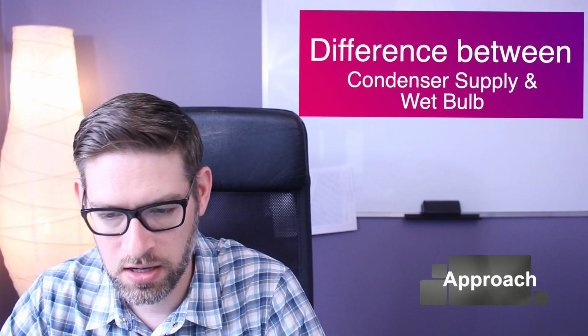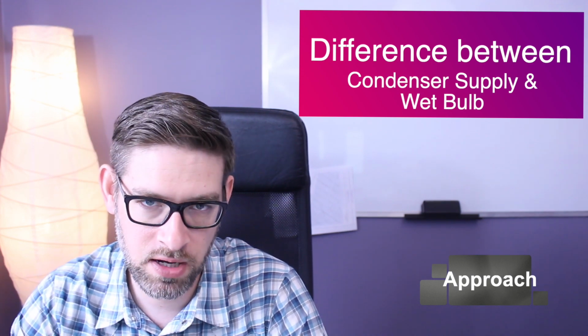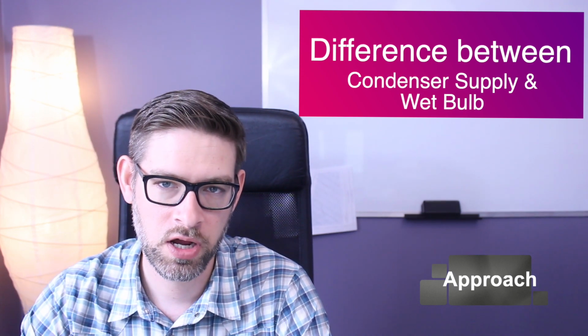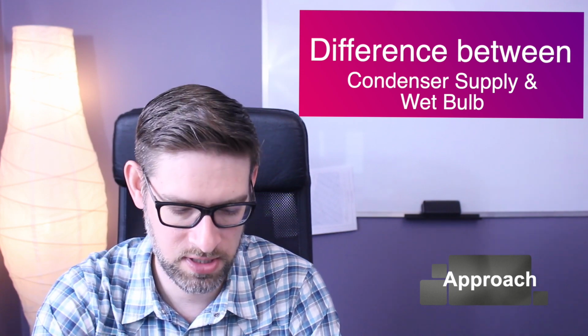Stay tuned. First thing that I want to cover here with respect to selecting and sizing cooling towers is just some terminology that we should be aware of before we get into that. And the first term that I wanted to cover is approach. Approach is the difference between the condenser water supply temperature and the outdoor ambient wet bulb temperature.